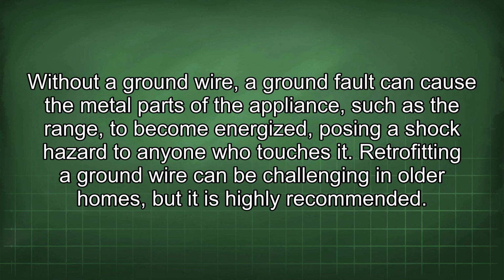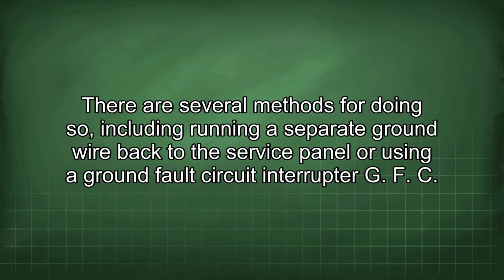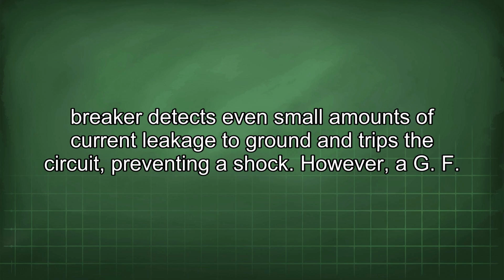Retrofitting a ground wire can be challenging in older homes, but it is highly recommended. There are several methods for doing so, including running a separate ground wire back to the service panel or using a ground fault circuit interrupter (GFCI) breaker to protect the circuit. A GFCI breaker detects even small amounts of current leakage to ground and trips the circuit, preventing a shock. However, a GFCI breaker does not provide the same level of protection as a properly installed ground wire, so it should only be used as a last resort.